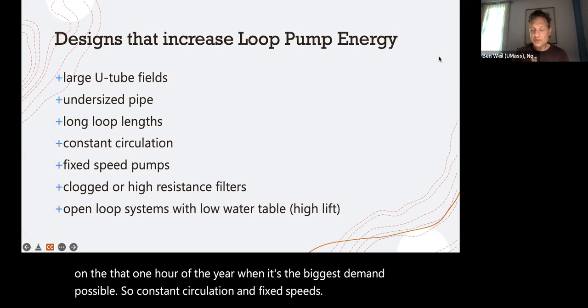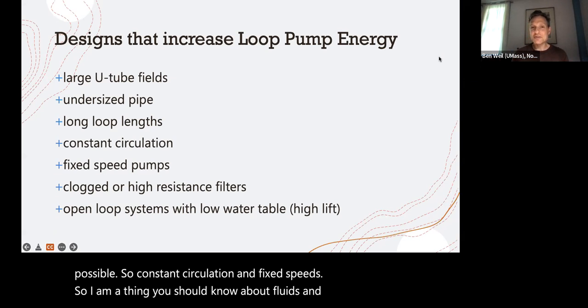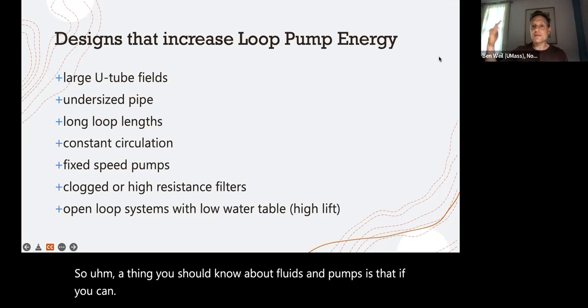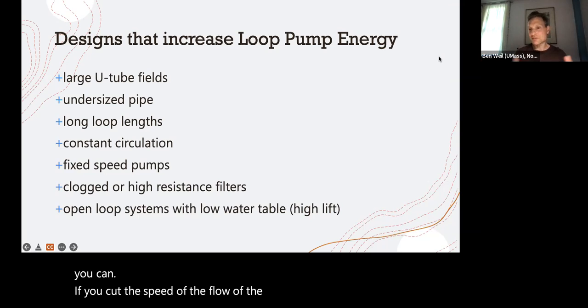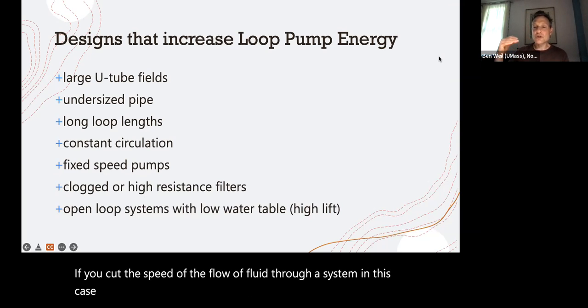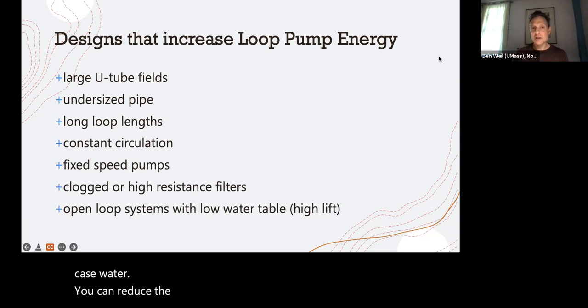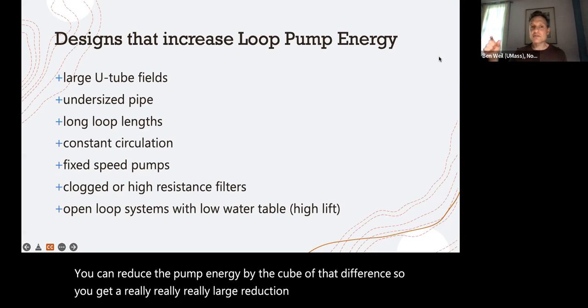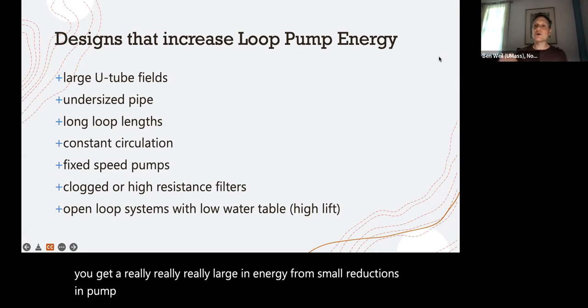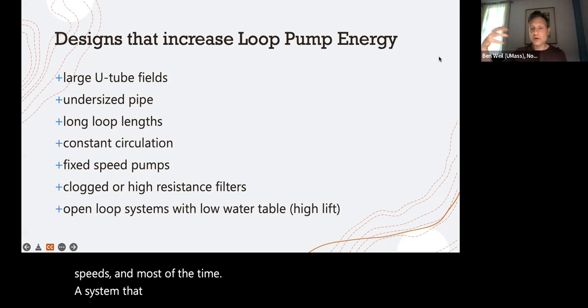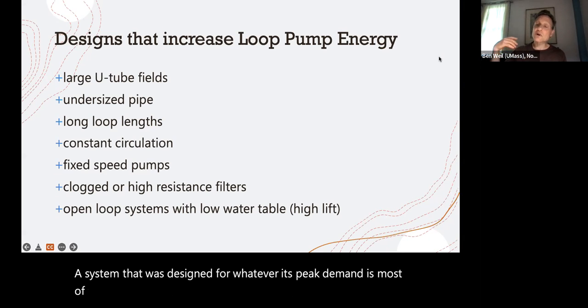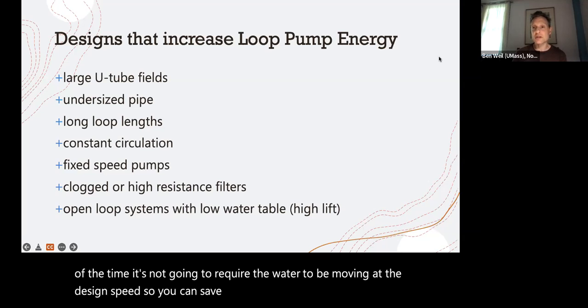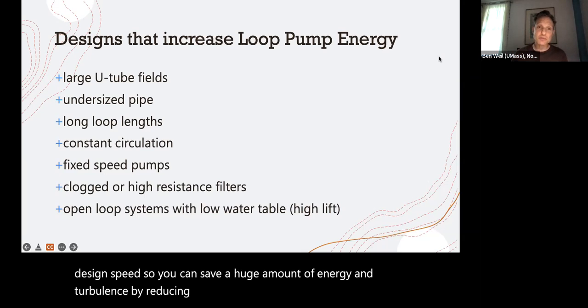A thing you should know about fluids and pumps is that if you cut the speed of the flow of the fluid through a system, in this case water, you can reduce the pump energy by the cube of that difference. So you get a really large reduction in energy from small reductions in pump speeds. And most of the time, a system that was designed for whatever its peak demand is is not going to require the water to be moving at the design speed. So you can save a huge amount of energy and turbulence by reducing the pump speeds and having them respond to the temperatures required by the heat exchangers.